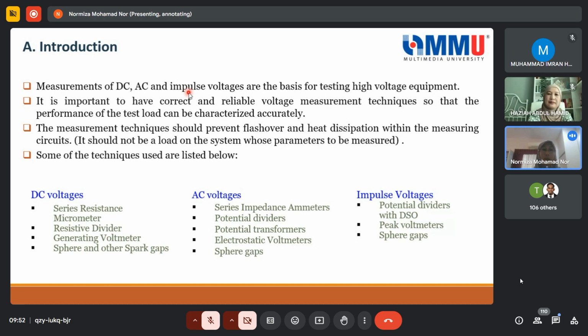So this very much relies on your measuring device. If your measuring device is not accurate, it means what is represented on your manufacturing data sheet may also not be accurate. So that's why it's important for this measurement, not only to understand, but also to ensure that it provides the correct reading and reliable reading. Okay, so that's why it is important to have correct and reliable voltage measurement techniques, so that the performance of the test load can be characterized accurately. Test load here refers to transformer, insulator, switchgear, all these capacitive equivalent circuit representations.